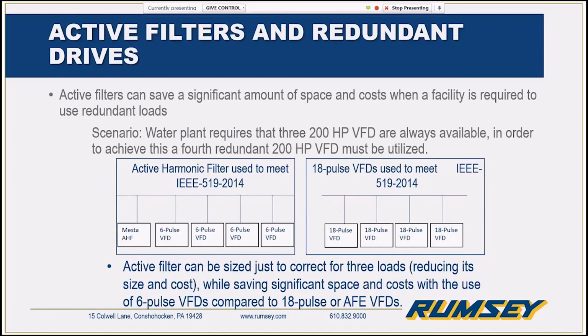And looking at the biggest cost savings that an active filter has over those others is if there are any redundant loads. So with water, wastewater, we see it all the time, but in many applications, we know the process can't stop, so you guys have extra drives sitting there that are ready to run if one goes down. So with this little example of having 4 VFDs and only 3 of them run, the active filter gets to be sized for just 3 of them, while the 18 pulse drive or the active front end drive, we'd have to have 1 for each of those loads. Good rule of thumb we've seen is 18 pulse drives are at least twice as big as their 6 pulse drive counterparts. So if you're looking here, we have 2, 4, 6, 8 space factors versus 1, 2, 3, 4, 5. So quite a bit of savings there for space and then for cost as well.